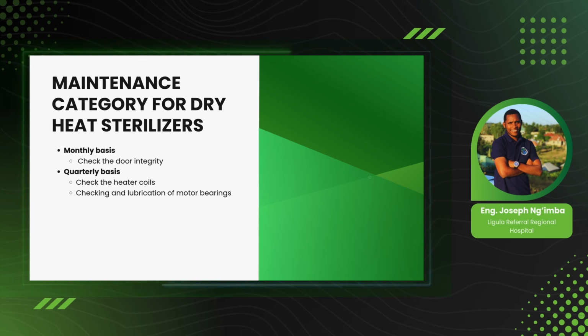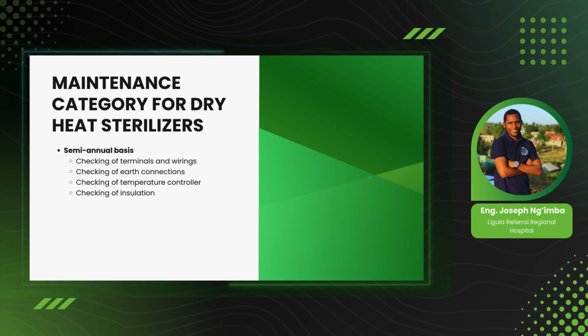So we check the fan and the fan motor. If needed, you have to lubricate. On a semi-annual basis, you check the terminals and wiring: the connections of wires between the terminals for the heating element, and the connection of wires with switches and controllers, we do on a semi-annual basis. Checking of the earth connection and checking of the temperature controller. Also checking the insulation material, if it is still intact, we do on a semi-annual basis.